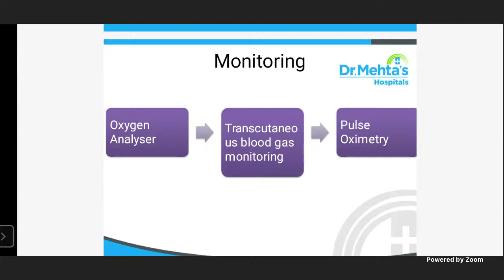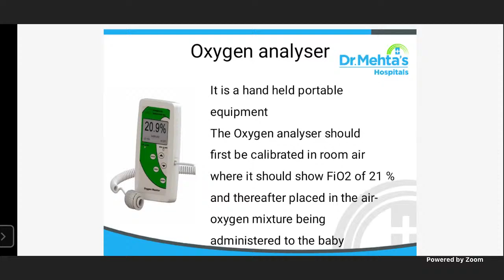And it should be first, before checking the FiO2 in the oxyboard, we have to calibrate the oxygen analyzer in room air. So it has to show 21%. Then only we keep it in the oxygen. If the baby is getting oxygen through an oxyboard, you can measure how much percentage the baby is getting and what the saturation is. Based on that, we can titrate the oxygen level.